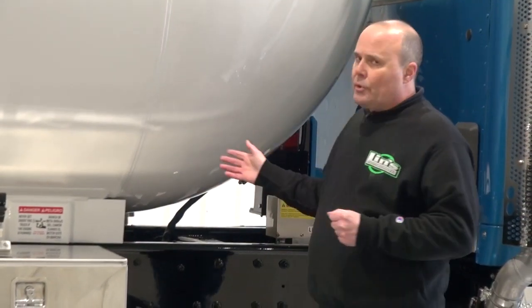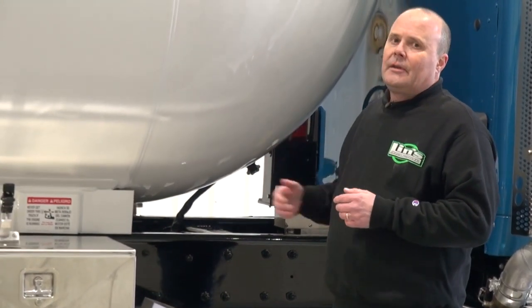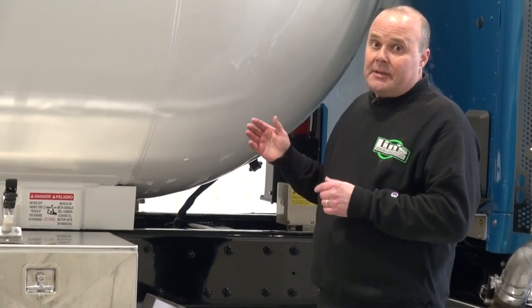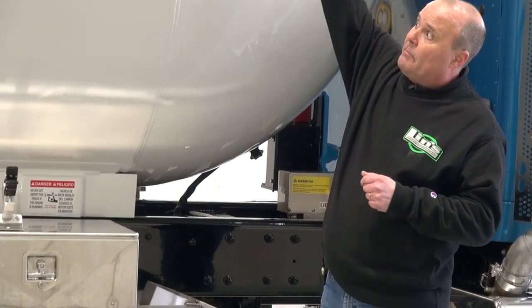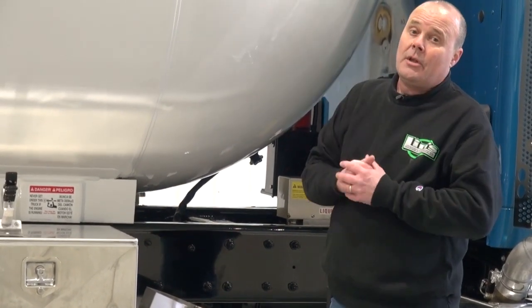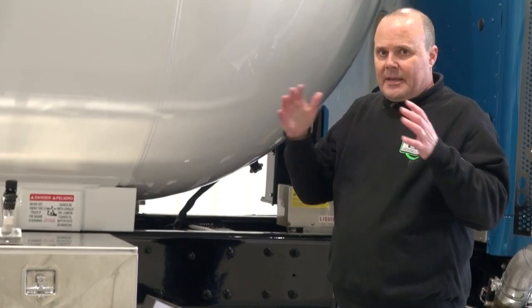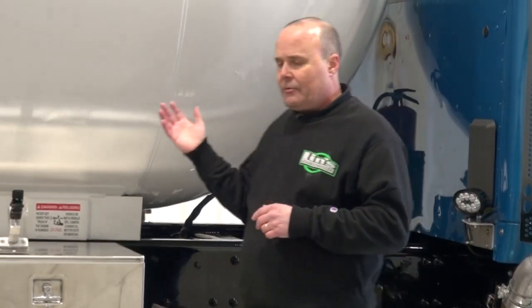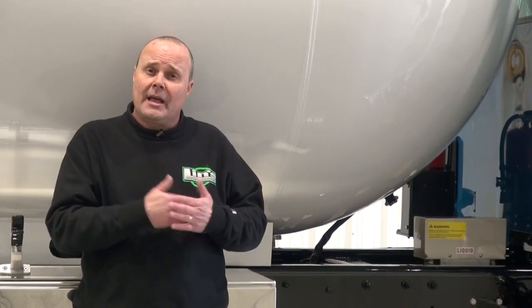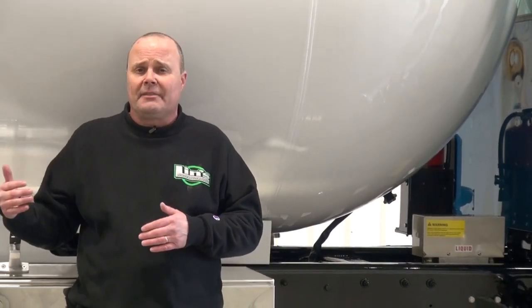It takes liquid propane from the pump, vaporizes it, puts it through the head of the tank, pipe back up to the vapor pressure on the top of the tank. That keeps the pressure up, keeps the liquid propane in the tank from wanting to boil. So the expansion rate for propane is 1 to 270. 1 gallon of liquid to 270 gallons of vapor.